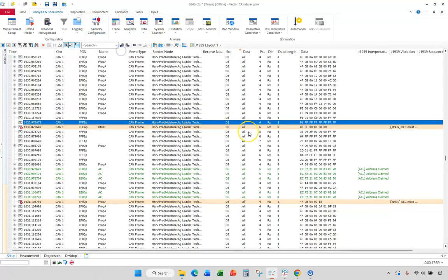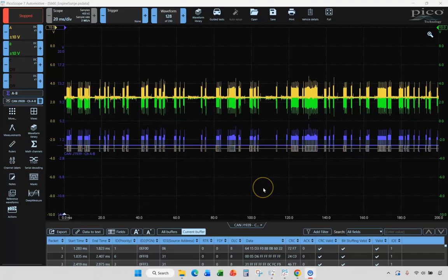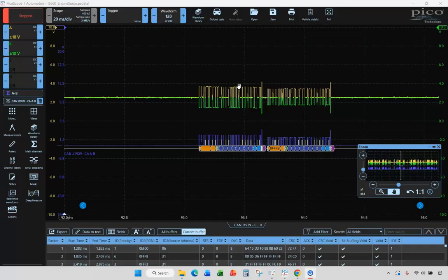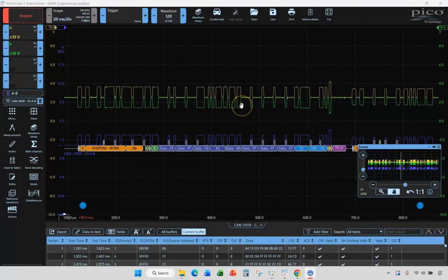So what I really needed was to get the data captured on Picoscope or something that's going to give me the voltage levels on that CAN bus to try to determine what's wrong. So we were able to get a Picoscope on this machine and to capture the data when the problem occurred. So you can see here, this looks good. This is a 250K CAN bus. There's my favorite controller, the engine controller, that's broadcasting information. This happens to be that PGN F004, which is engine speed.